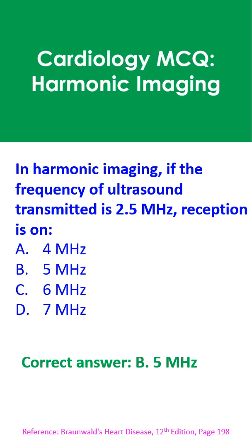In harmonic imaging, reception is on the second harmonic frequency, like 5 MHz for a 2.5 MHz transmitted signal. Interference and artifacts are lesser, resulting in better image quality.